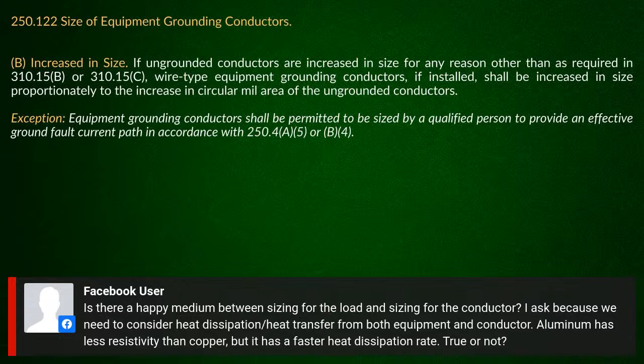Yeah, and we have this question come in. Is there a happy medium between sizing for the load and sizing for the conductor? I ask because we need to consider heat dissipation, heat transfer on both equipment and conductor. Aluminum has less resistivity than copper, but has faster heat dissipation rate.